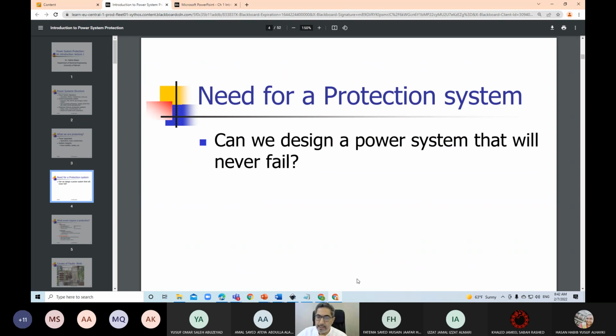Can we design our system so that it will never have a fault, so it will never fail? Can we? Is it possible, guys? I think it's impossible. It is impossible to have a system without faults, Doctor. Yes, impossible. Okay, good. Even if it were designed, it would be very, very expensive, meaning I would have to build a lot of redundancies. If one fails we have the other, so faults would happen.